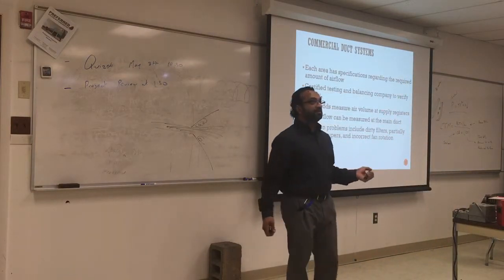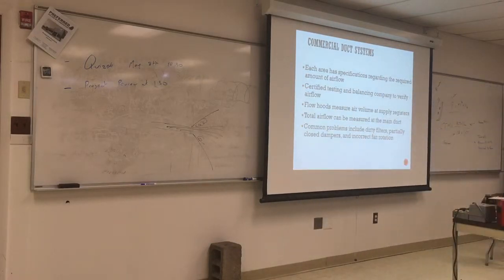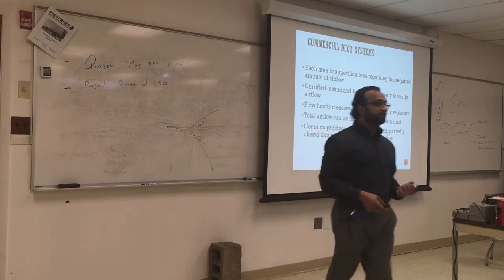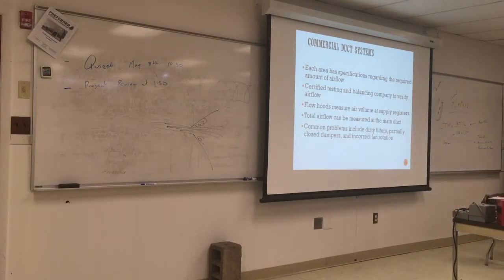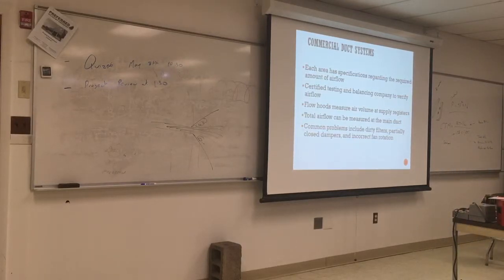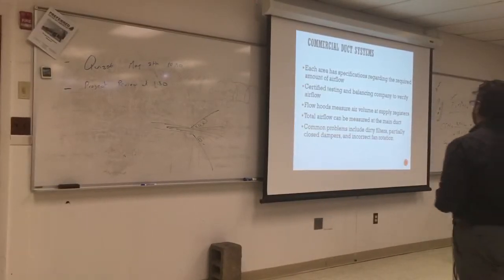Flow hoods measure the air going at the supply register. If you were in the TAB class, probably you used the hood to cover the register and give you the air flow. Total airflow can be measured in the main duct. How do you measure the flow in the main duct? You don't have a velocity meter or a hood to put in there. It's a big duct. You put the manometer inside and you measure the pressure, the velocity pressure. Then you calculate the air velocity.